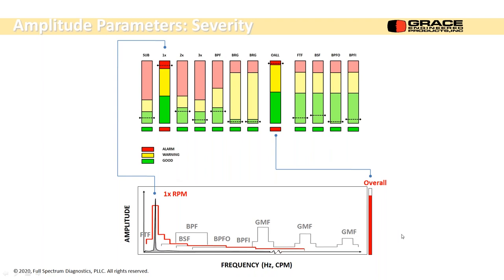There's different frequencies that are bound to show up based on the design of the machine. So there's one times RPM, there's blade pass frequency, there's gear mesh frequency. You're popping up a packet of overall energy information from this chart, basically, every second, every time you collect data off your machine. And it comes up as a kilobyte package or whatever into the cloud. There is a way you can probably do that with each frequency you're interested in. So this is one, two, and three times harmonics. There's subsynchronous, there's blade pass. If you know what the bearing is, you can put those values in and upload just that tight frequency band instead of the whole spectrum. I believe the spectrum's calculated originally, and then if you just filter off different sections, you can get all kinds of statistical information on discrete frequencies in the spectrum.